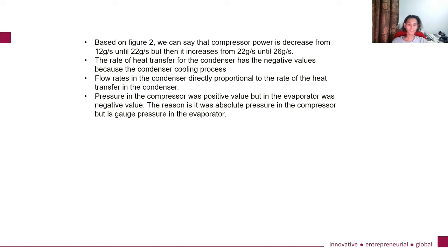Pressure in the compressor was a positive value, but in the evaporator was a negative value. This is because it is absolute pressure in the compressor, but it is gauge pressure in the evaporator.